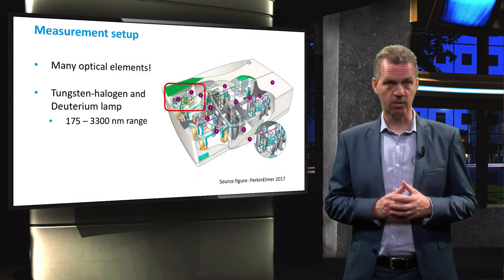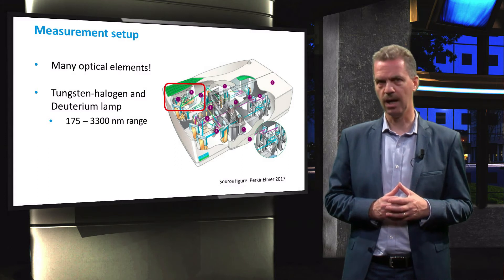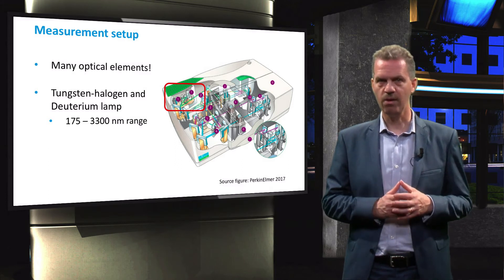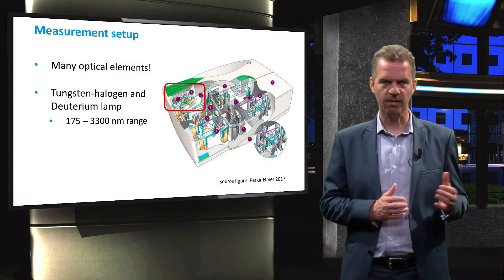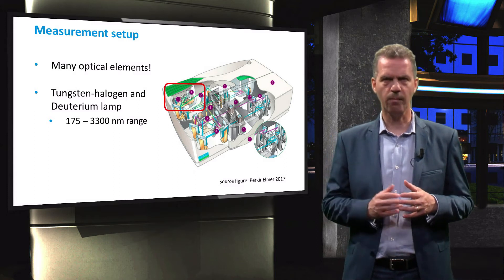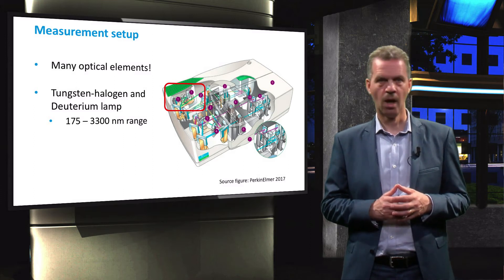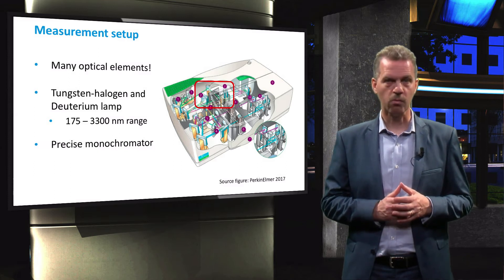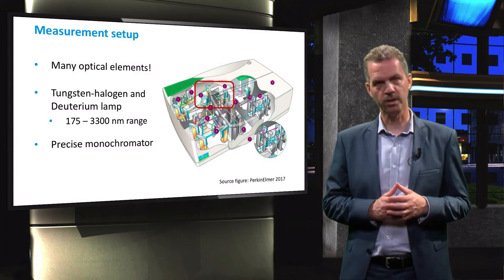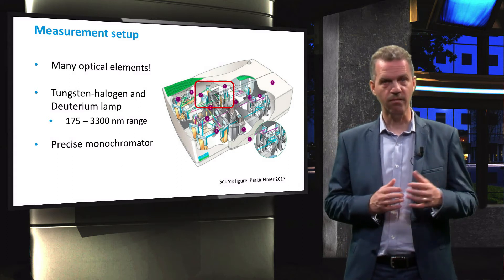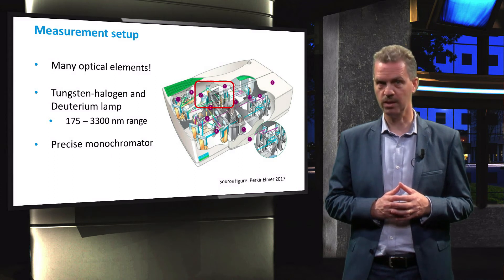The light sources in the instrument are a tungsten halogen lamp and a deuterium lamp. Together with very precise optical components, the test spectrum ranges from 175 nm all the way up to deep infrared at 3300 nm. The instrument can produce monochromatic light with a resolution smaller than 0.20 nm, which means that the given wavelength varies only within a bandwidth of 0.20 nm.